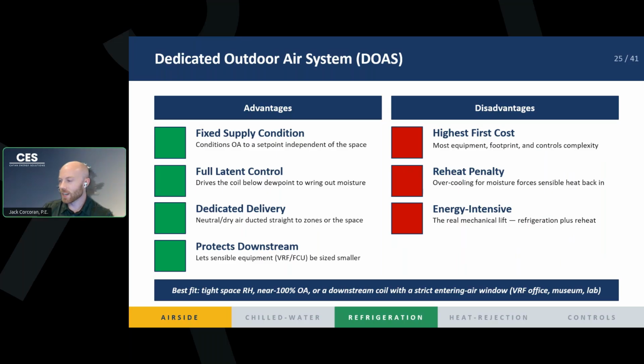And I guess this last point is more important for VRF systems, right? We talked about how they don't handle latent loads very well, right? They don't achieve a super low coil temperature all the time because they can vary the speed of the compressor and you don't get as low of a temperature. Essentially, DOAS is required when you use a VRF system, because your VRF system is not going to wring out the moisture if you use an ERV or just dump the outside air into it. You'd have to have a very low amount of outside air if you wanted to use an ERV or outside air fan with a VRF system. So essentially, it allows you to have your secondary coil sized for sensible, and this DOAS unit will be sized for the latent load.